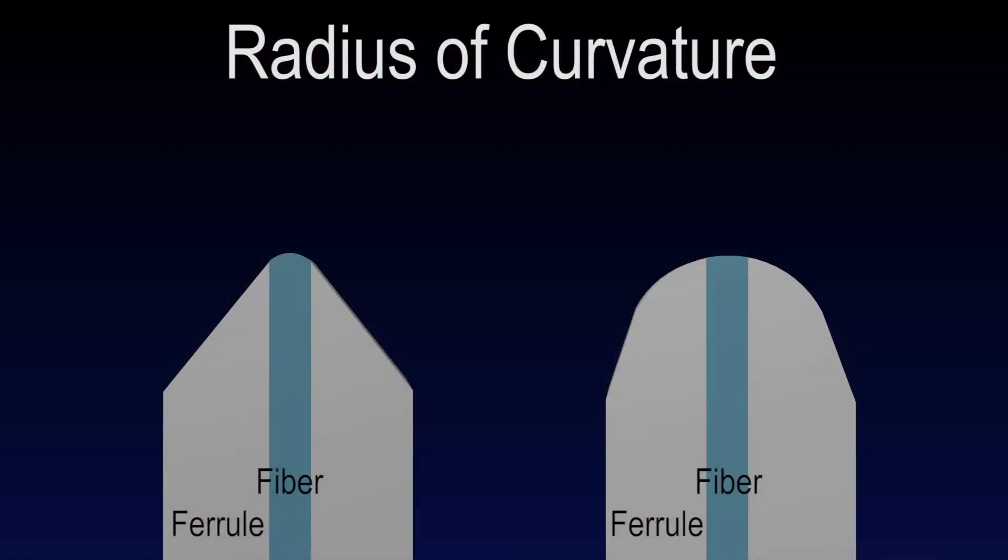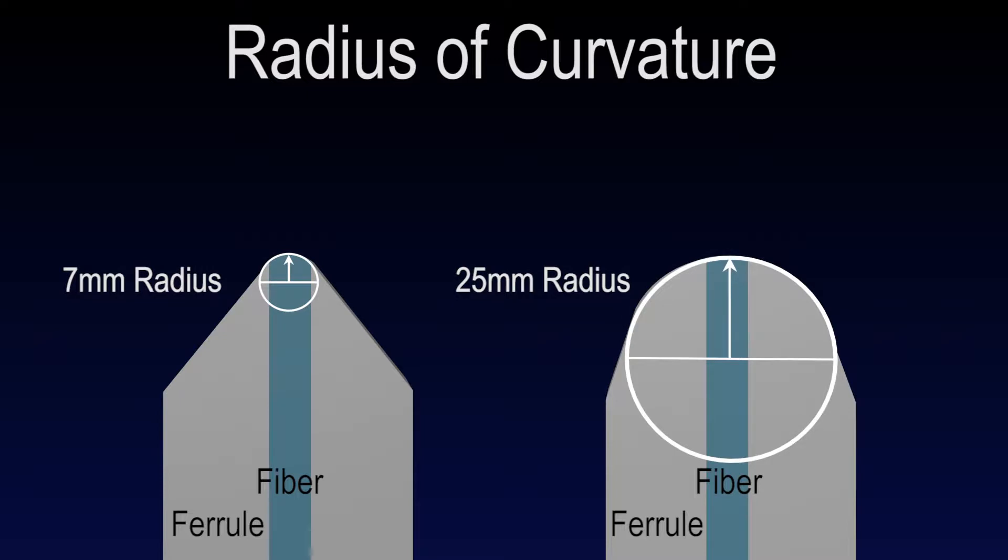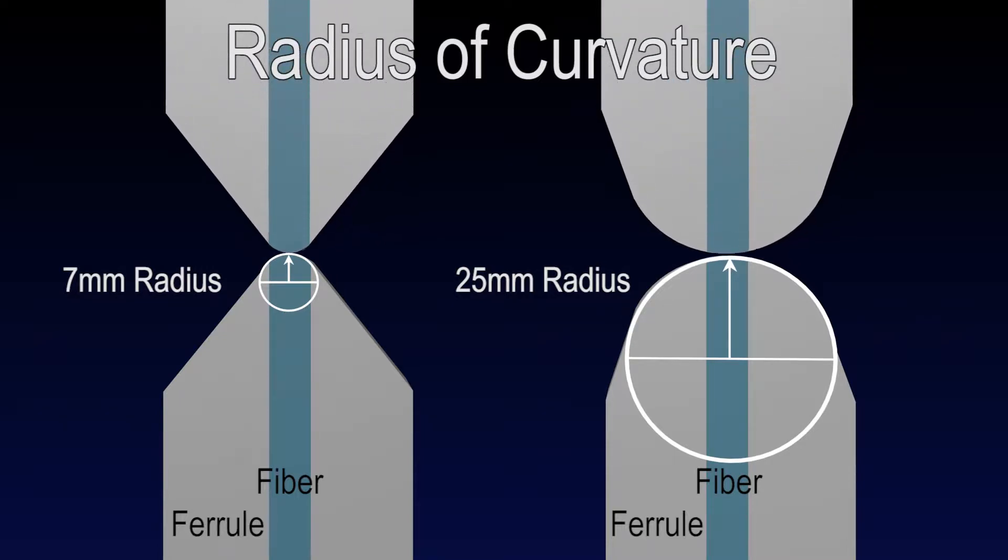Ferrule end-faces are domed to ensure the contact area between mating connectors is at the center of the ferrule where the axis of the fiber core is located. The radius of this dome is called the radius of curvature. If the radius is too small, there will be a smaller contact area between fibers which places more force on the fibers during mating. If the radius is too large, physical contact between the fibers may not be achieved due to a larger contact area.